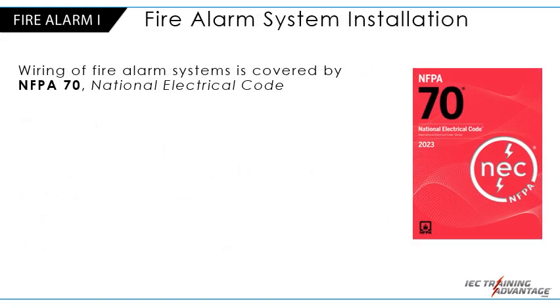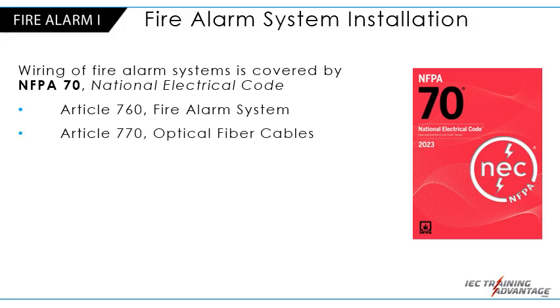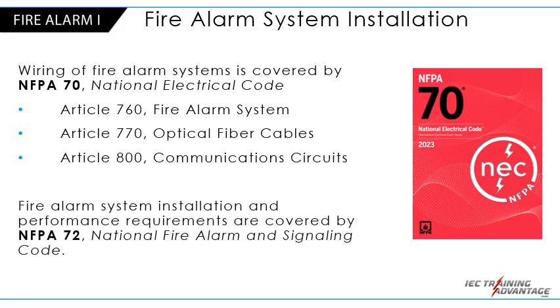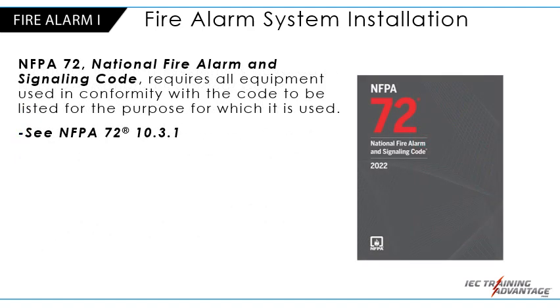Fire alarm system installation. Wiring of fire alarm systems is covered by NFPA 70, the National Electrical Code, and articles that may apply more specifically to fire alarm are Article 760, Fire Alarm Systems; Article 770, Optical Fiber Cables; and Article 800, Communication Circuits. Fire alarm system installation and performance requirements are covered by NFPA 72, the National Fire Alarm and Signaling Code. NFPA 72 requires all equipment used in conformity with the code to be listed for the purpose for which it's used. See NFPA 72 10.3.1.